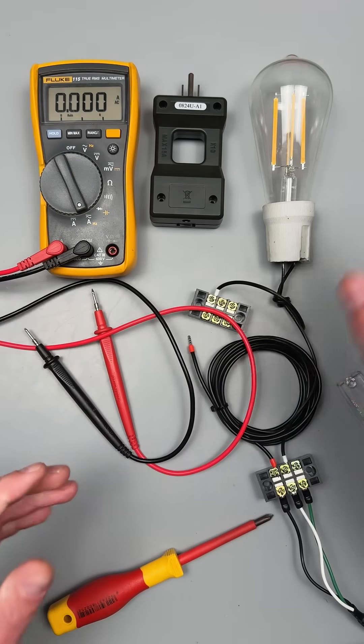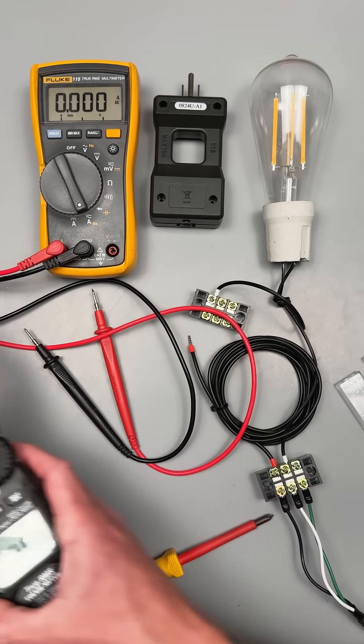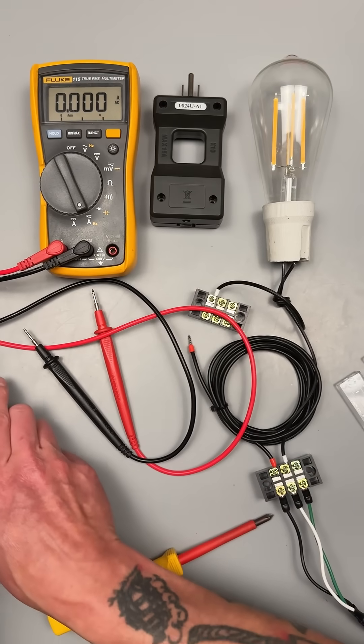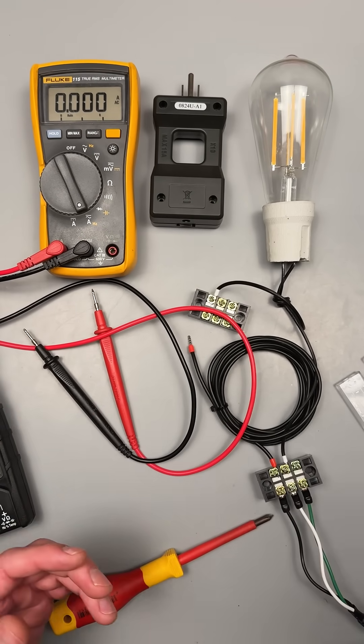With the times 10 and divided by 10, we got much more consistent and accurate readings from all of our clamps, regardless of manufacturer. I hope that makes sense and helps.